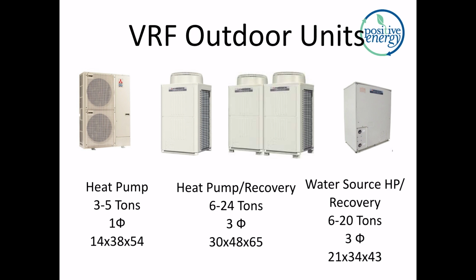Third category is water source heat pumps and heat recovery equipment. Again, the sizes and the three-phase could be considered predominantly for commercial applications, though not impossible for residential, but we'll talk about converting from single to three-phase in a moment. What I really want you to take away from this slide is that there are heat pumps, whether they're air or water source, and then there are these units that they refer to in the industry as heat recovery systems. Heat recovery means they can provide simultaneous heating and cooling. It's a very exciting, very efficient way to move heat and cooling around a building, especially if there's a lot of diversity in the building, which many buildings have, a lot of commercial buildings particularly.